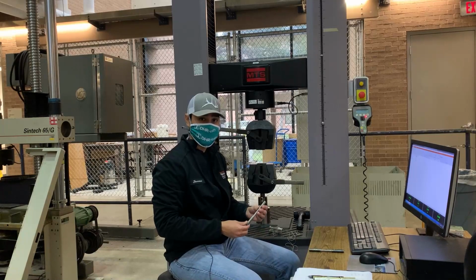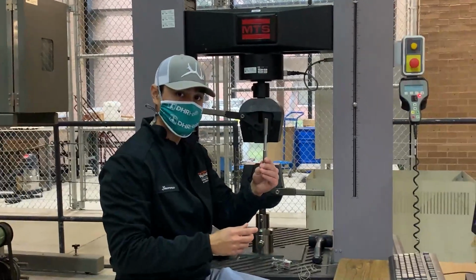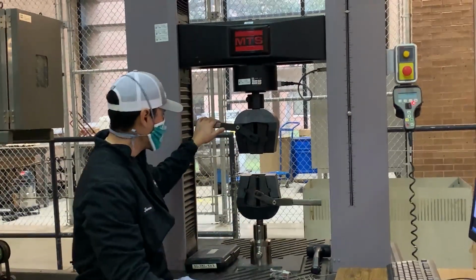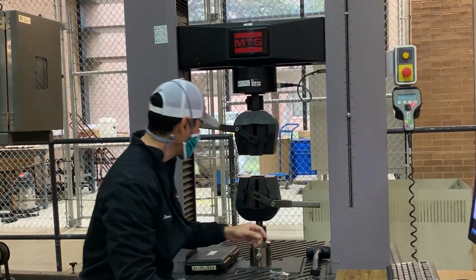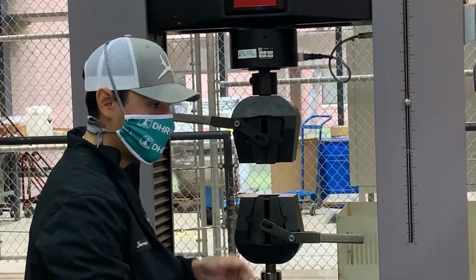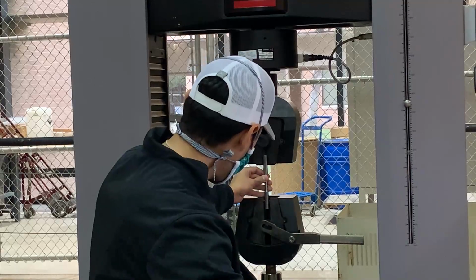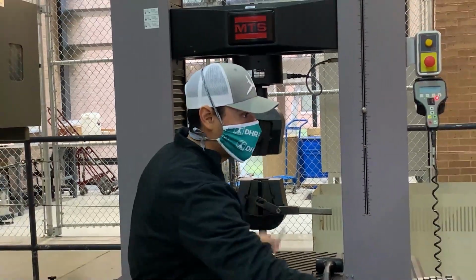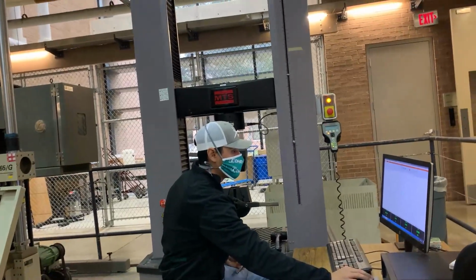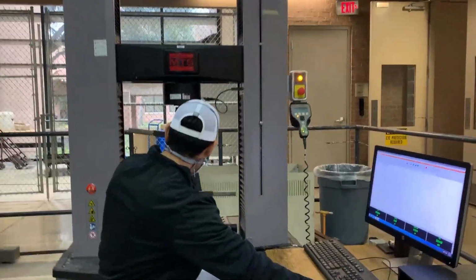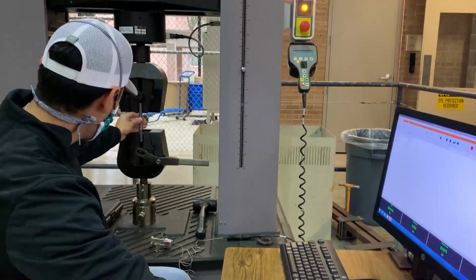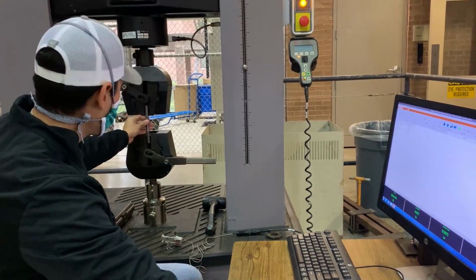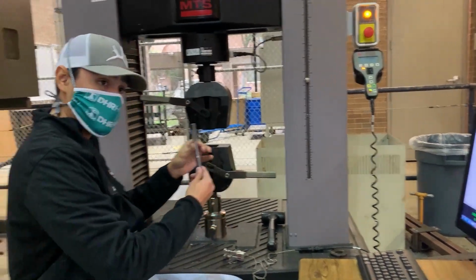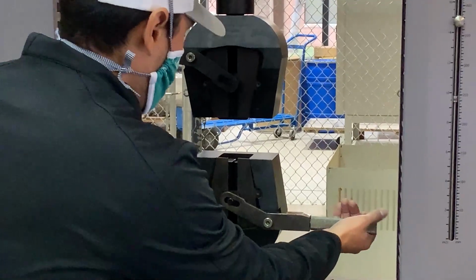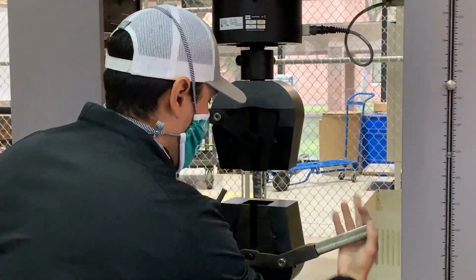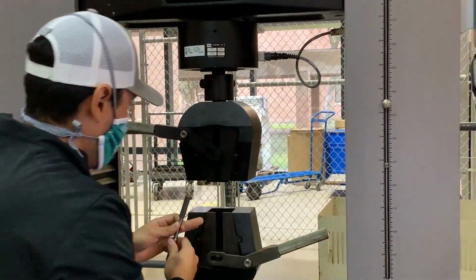Right, so when we begin our test, we're gonna take our specimens and place them in the locking jaws. You wanna try to get these as close to the center as possible. I'm gonna bring the crosshead down just a little bit here, just to get my sample a little bit closer. So you wanna place your sample as best as you can inside, in the middle.